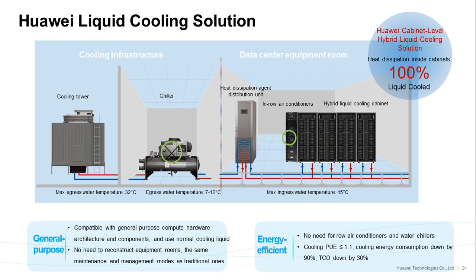Previous V3 servers do not support 100% heat dissipation through liquid cooling, and some air-cooled devices must be used, such as chassis fan modules and row air conditioners. Now the V5 servers support cabinet-level liquid cooling and no longer need row air conditioners. A row air conditioner is configured for a row of cabinets, and such conditioners are used in most traditional data centers.